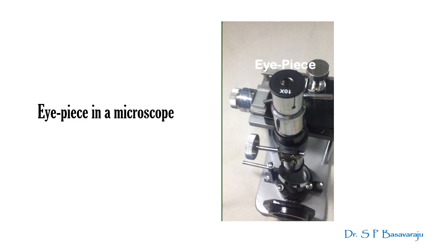It is stuck by a glue on an annular ring-like support mounted inside the tube. If the cross lines are seen clear and sharp, then the reticle is under proper focus. If they look blurred, then keep looking. Hold the eyepiece at its top and slide it gently up and down. The sharpness changes. Stop when it looks sharpest. Leave the eyepiece and it stays there.